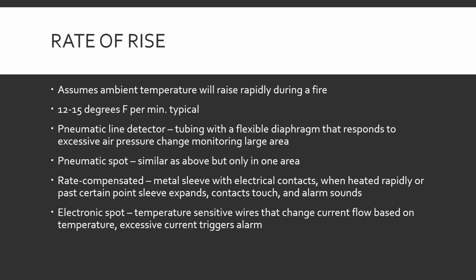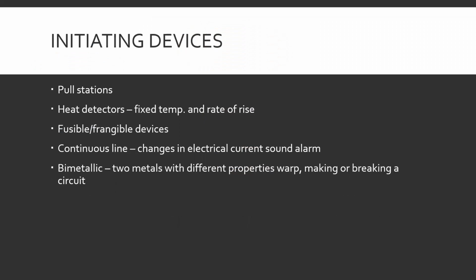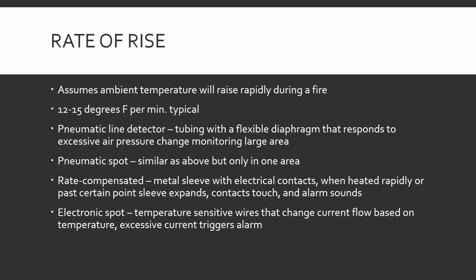Electronic spot. Rate of rise. Temperature sensitive wires that change current flow based on temperature. Excessive current triggers the alarm. Continuous line. Where wires in a little tube heat, melt the insulation, change the properties of the metal, and lower their resistance to current. A change in electrical flow, and the alarm sounds.